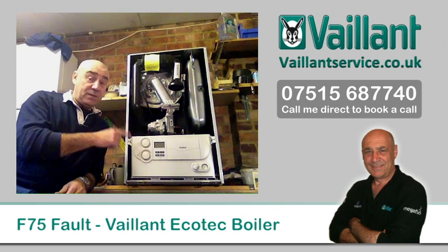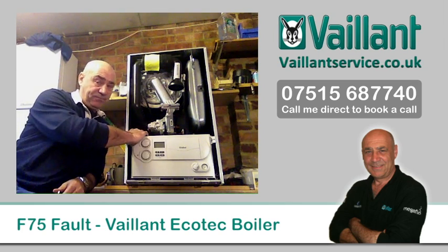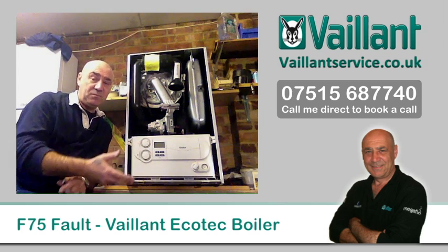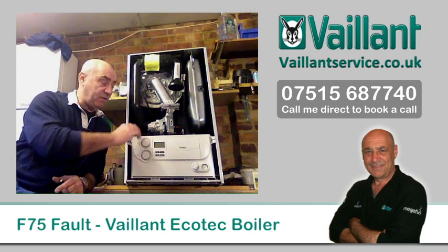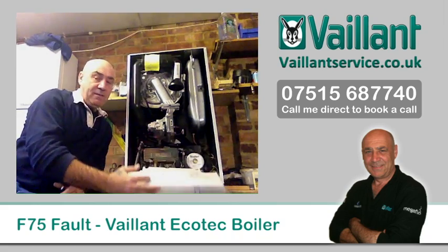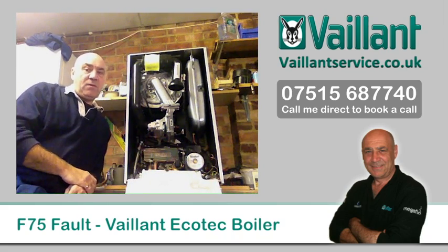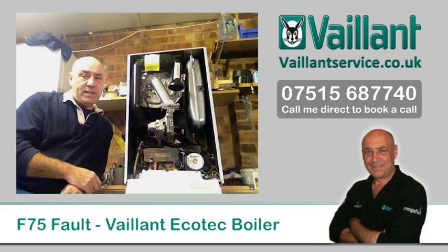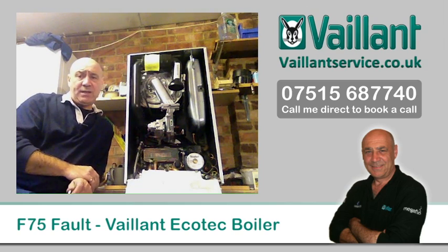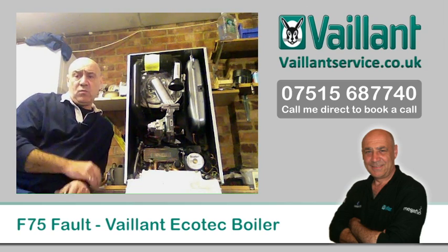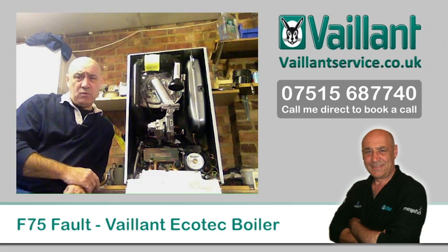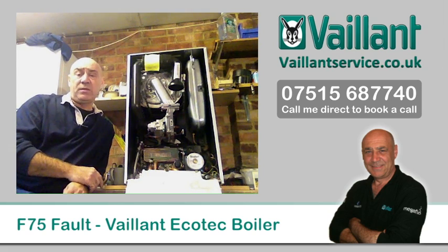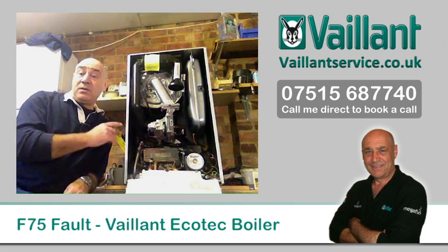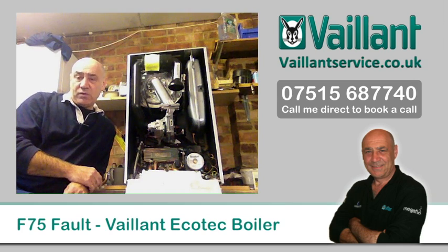So, the Ecotec F75 fault code comes up in the display, you reset, the boiler tries to restart, and flashes up the F75. Let's have a look at where the F75 comes from and what it is. Boilers are just like kettles. You wouldn't want to put your kettle on without putting any water in it, and exactly the same principle applies to all boilers. If a boiler comes on with no water in it, you're looking at quite a hazardous situation, so you don't want that to happen.